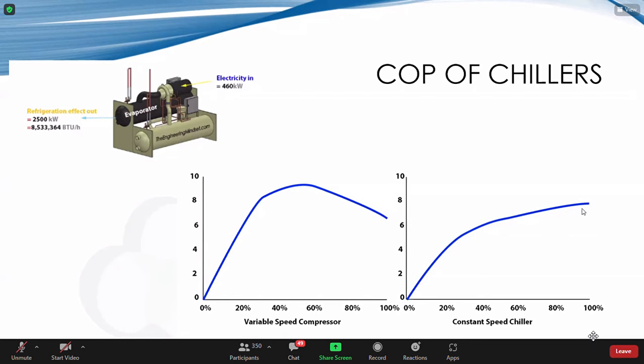Most of these chillers actually operate at 40 to 60%, especially now during the pandemic, it's even lower, maybe 20 to 40% or so, depending on the demand flow. So with a lot of R&D work and real world cases, it has been settled that variable speed or demand flow trumps constant speed.